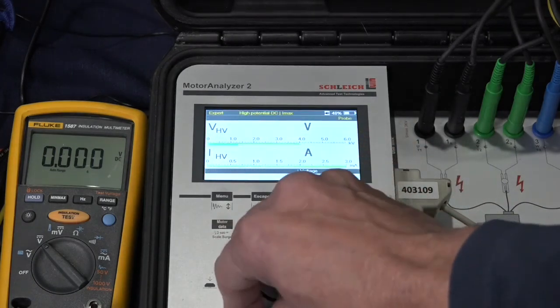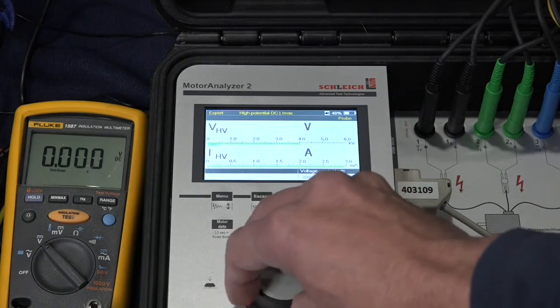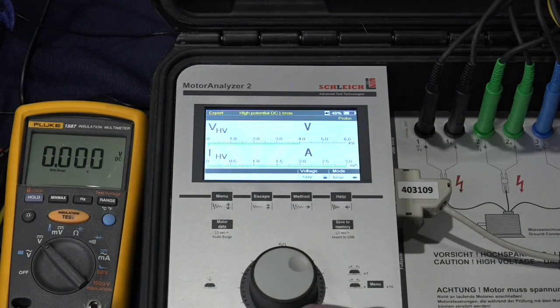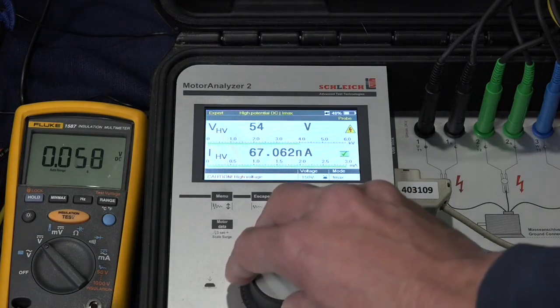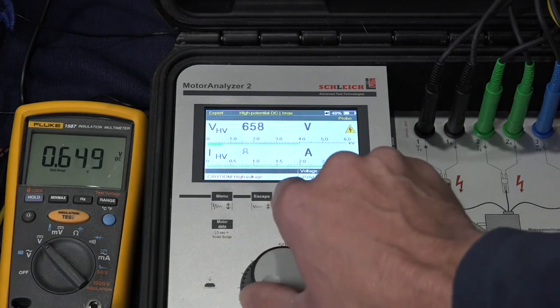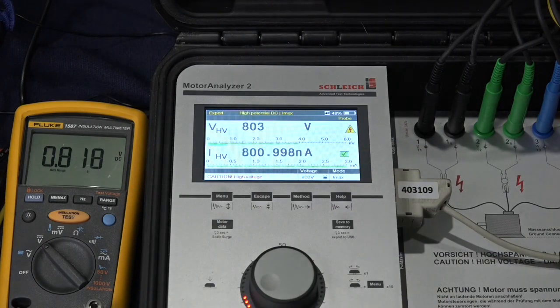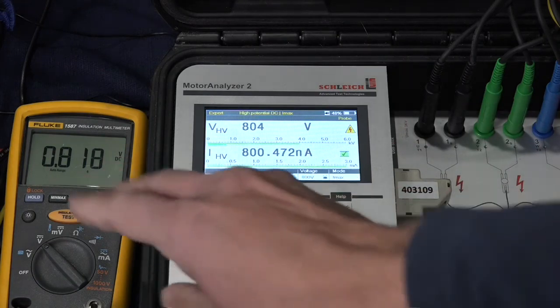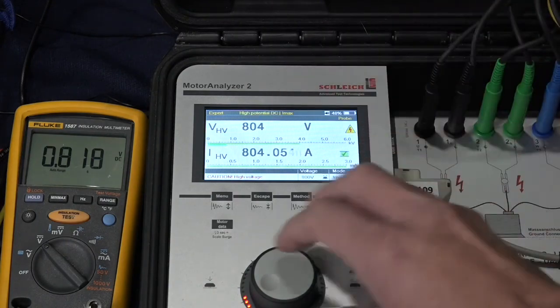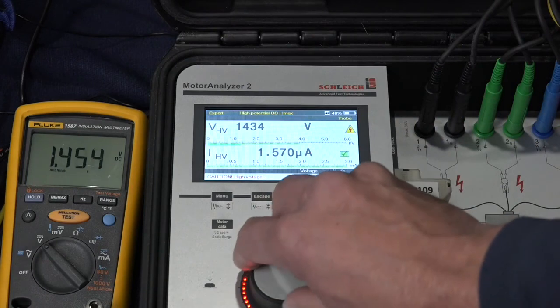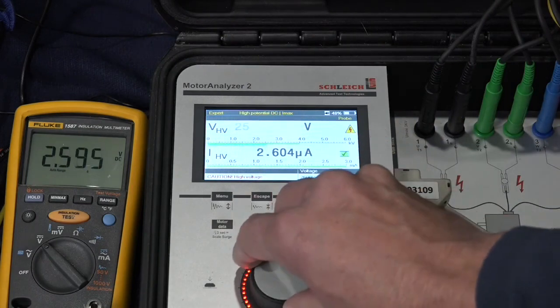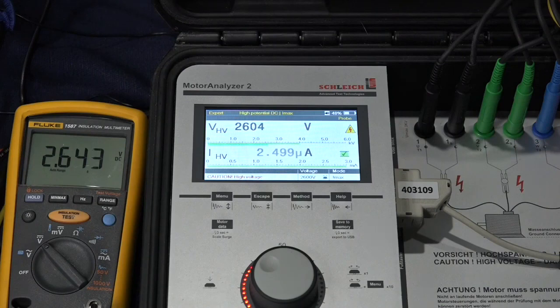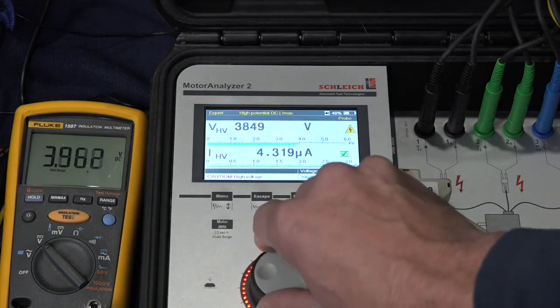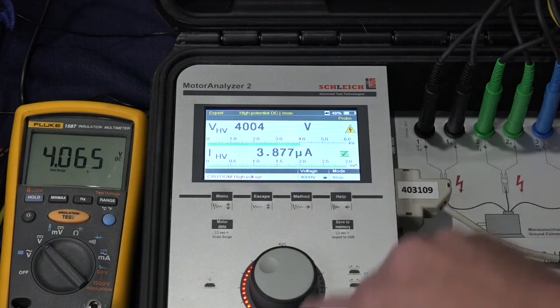Now I'm going to start it down low to begin with. Start the test. Ramp the voltage up. And you can see there on the left-hand side of the video that there's a voltmeter showing the voltage that's actually being impressed on the machine. It's saying 818 volts. The MA2 is saying 804. That's pretty close. Let's continue to bring this up. 2600 volts. Let's go to 3000. Working pretty good. All the way to 4000. So of course, let me stop the test.